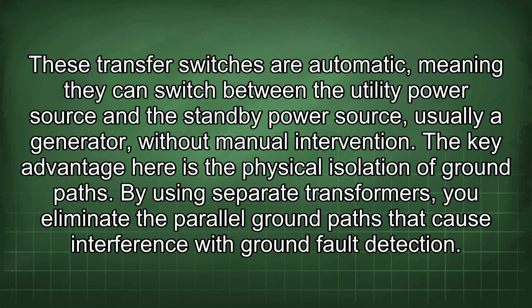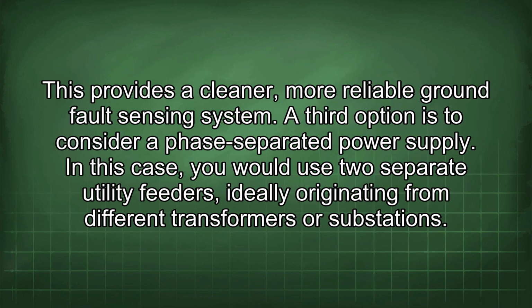The key advantage here is the physical isolation of ground paths. By using separate transformers, you eliminate the parallel ground paths that cause interference with ground fault detection. This provides a cleaner, more reliable ground fault sensing system.